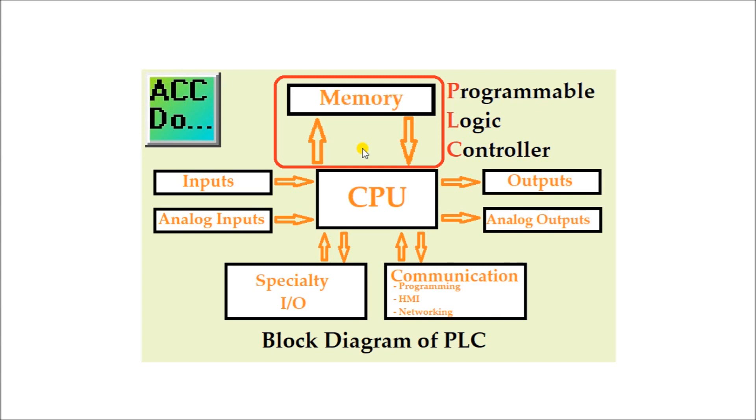The operating system itself in the PLC is held in non-volatile memory, which is also called firmware. To change the firmware on a PLC, you will need to flash or download that program. This is usually done using the programming software for the controller. It is important to ensure that the flashing of a controller is not interrupted. Interruption of the flash can cause the PLC to stop functioning, which is also referred to as bricking the PLC.